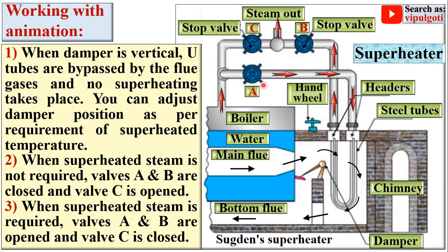When superheated steam is not required, valves A and B are closed and only valve C is open. In this case, steam is taken from the superheater outlet but it is wet steam coming directly from the boiler, without passing through the U-tubes, so it remains in the form of wet steam.